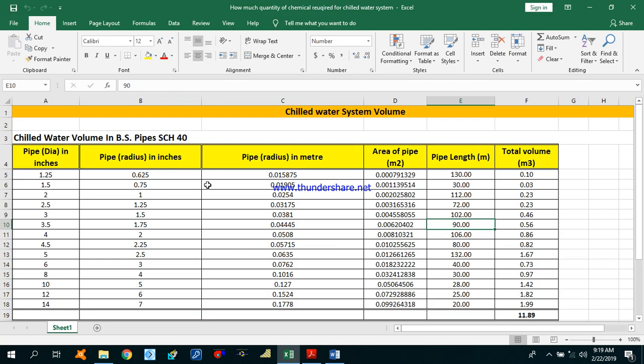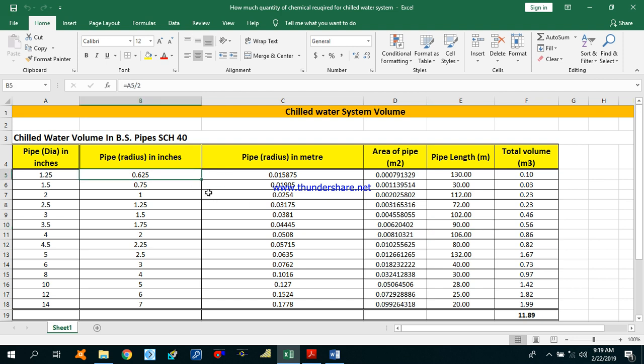I have made an Excel sheet for chilled water system volume calculation. Before starting the calculation, I will explain why chemicals are required for the chilled water system. We need to put the chemicals because we need to prevent the system from corrosion, scaling, fouling, and microbiological growth.